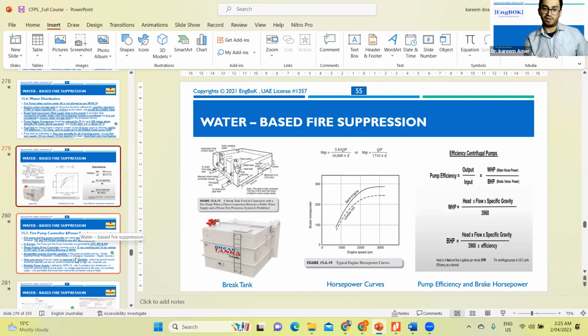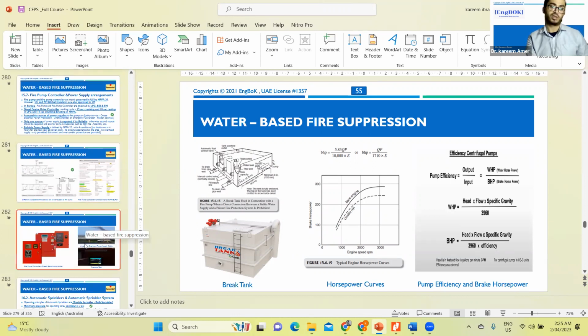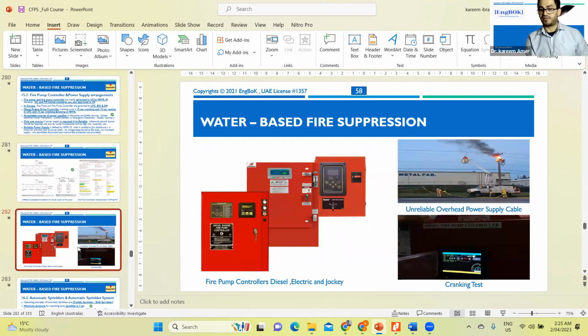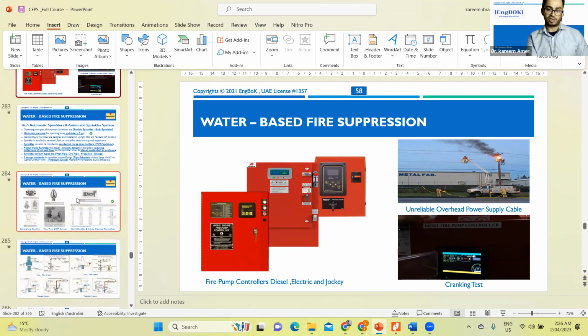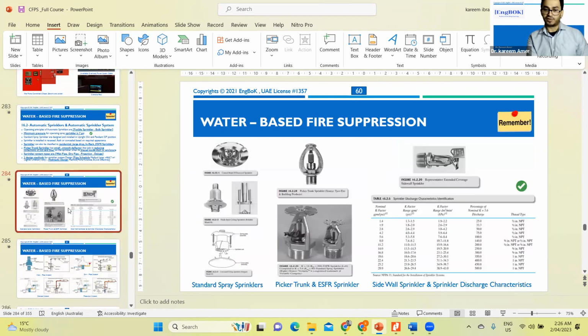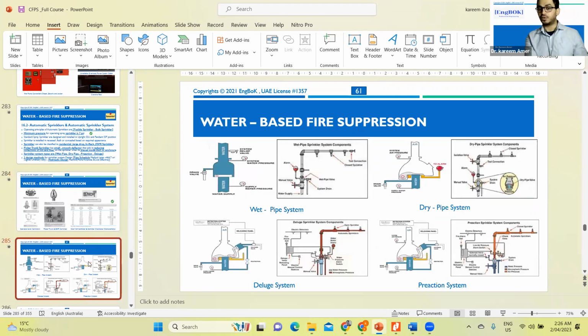What is the break tank? How do you differentiate a break tank from the normal suction or elevated tank? What is the fire pump controller for jockey, standby, like diesel, and main, like electrical? Cranking test, and reliable and unreliable power supply. Sprinkler types for different applications, either maybe storage, maybe different standard spray sprinkler, pendent, upright sprinkler: how do you select the proper type, and what is the K factor, how do you get the K factor, what is the basics behind the K factor, with the discharge coefficient, with the size of sprinkler.